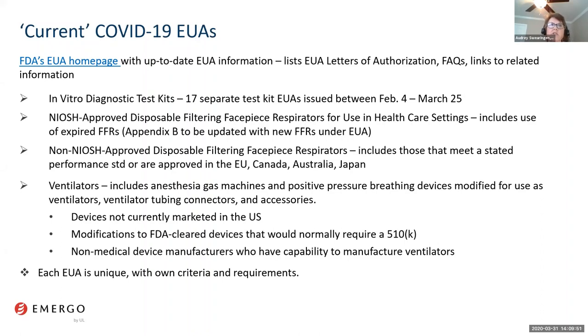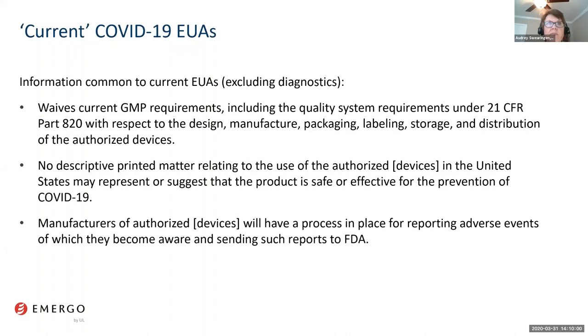I do want to point out that each emergency use authorization is unique and it has its own criteria and requirements. Next, please. However, there is information that's common to all of the existing EUAs in place, excluding the diagnostic test kits. The other device EUAs that have been released all waive the current good manufacturing practice requirements, including those of the quality system regulation with respect to the design, manufacture, packaging, labeling, storage, and distribution of the authorized device under each given EUA.